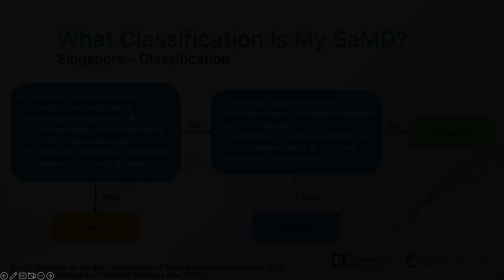And this flowchart is based on the current risk classification rules as per GN 13. For the manufacturer to determine the risk classification of telehealth medical devices, the first question is to see if the device is intended for continuous monitoring of physiological parameters, providing therapy recommendations, modifying ongoing therapies, or diagnosing, monitoring, managing, or treating critically ill patients. If the answer is yes, then the device is Class C. If not, let's move to the second question. The second question is: is the device intended to measure physiological parameters in diagnosis, or administer or exchange energy in a non-hazardous way? If the answer is yes, the device is Class B. And if no, the device is classified as a Class A device.